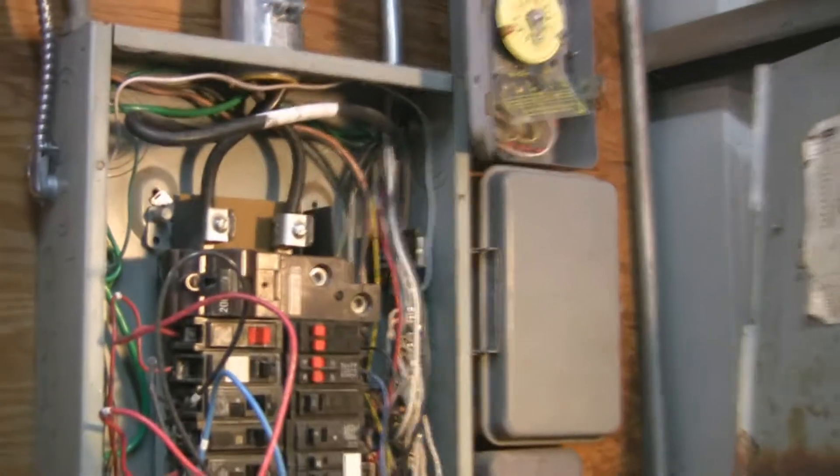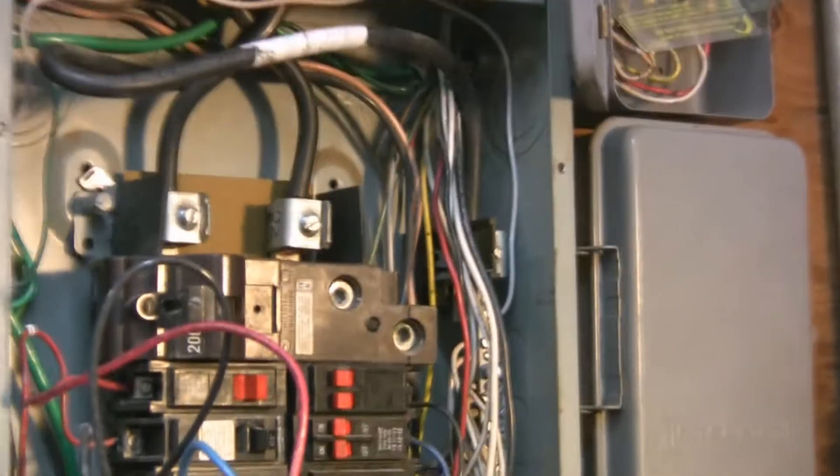Just taking a look at that old panel, you can see why it needs to be replaced. Right now I've got it temped in, but that 200 amp breaker I can't even turn it on and off anymore. So I've got it fed through the main lugs only.